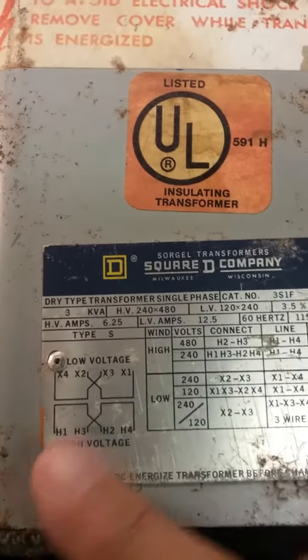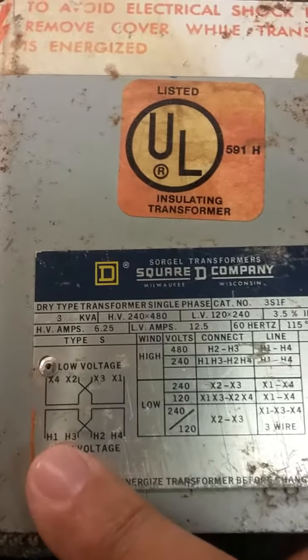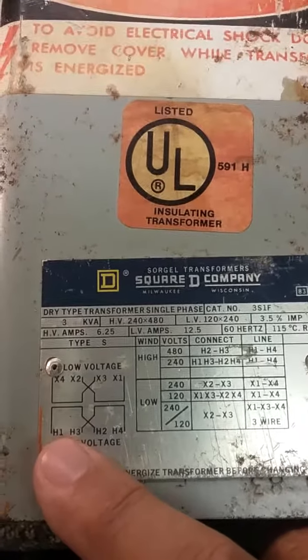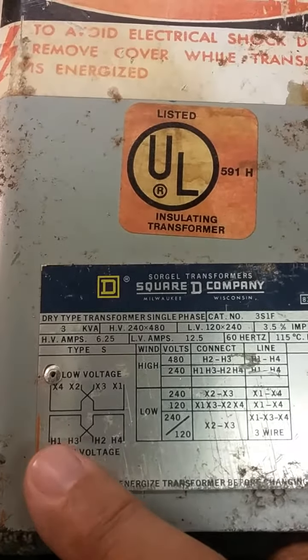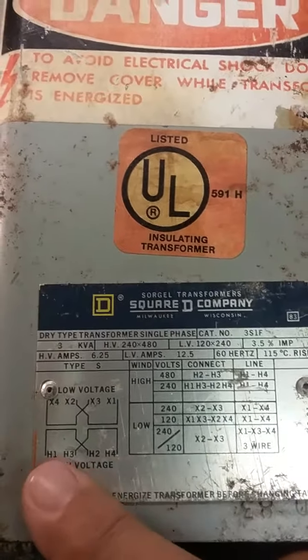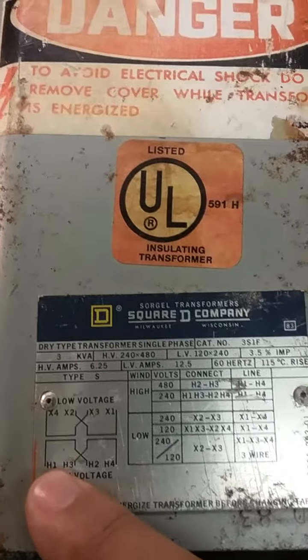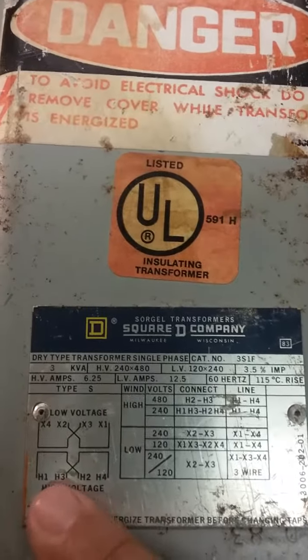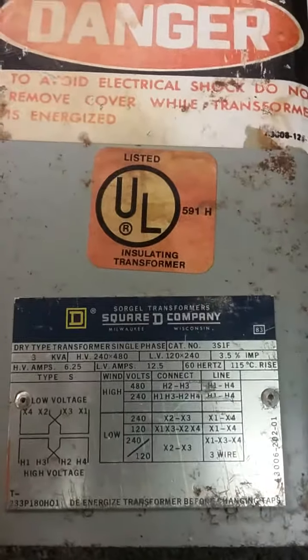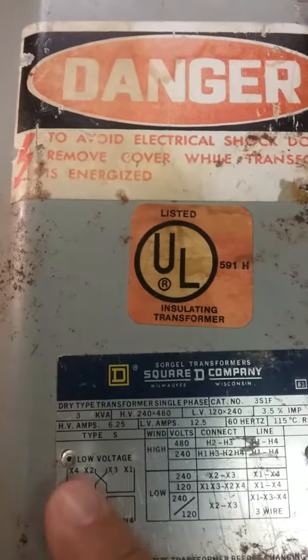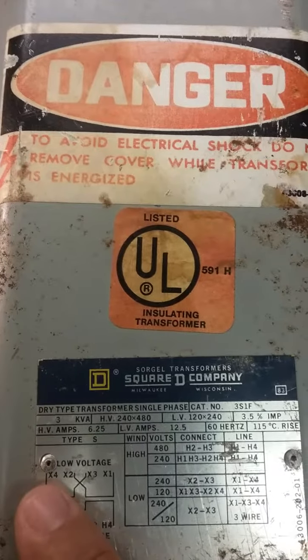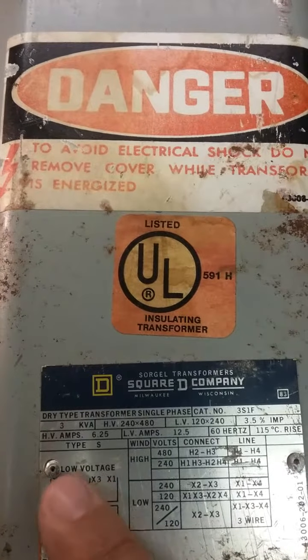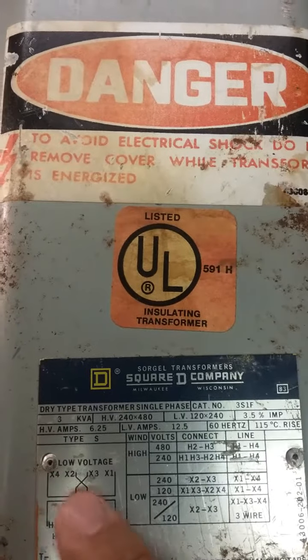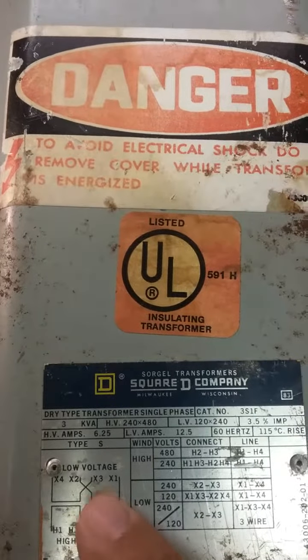As you can see here on the input, on the primary, you have two coils. There's H1 to H2 and H3 to H4. On the secondary, or the output, the low voltage side, you have X1 to X2, X3 to X4. So there's two coils on the secondary and two coils on the primary.